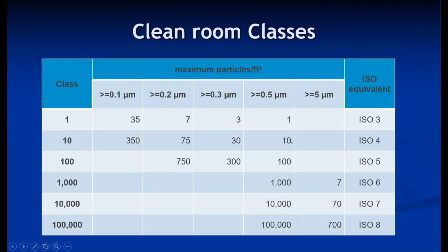As per the applicable ISO standards, from ISO 3 to ISO 8, clean room classes are mainly designated based on the permissible particles of size greater than 0.5 microns.